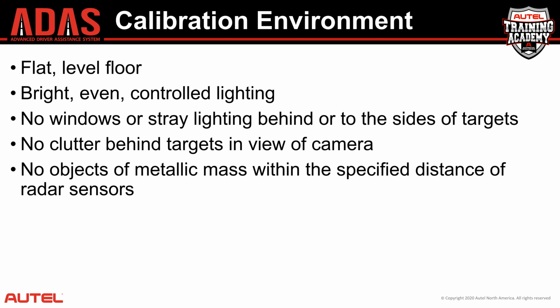So no windows or stray lighting behind the targets or coming from the side of the targets. It'll cause glare that will throw off the camera. Windows or lighting behind the targets can actually blind the camera and it won't be able to see the target. So the calibration will actually fail. No clutter behind the targets in view of the camera. What they're really talking about is clutter that could be picked up by the camera as being a target. And keeping in mind that many cameras see in grayscale, anything that could turn out to look like a black and white or grayscale checkerboard pattern can confuse the camera and cause it to either fail a calibration or calibrate inaccurately. So you may get the message calibration completed successfully, but it may not be accurate because the camera may have calibrated off of something other than your target. It's actually a very common occurrence.